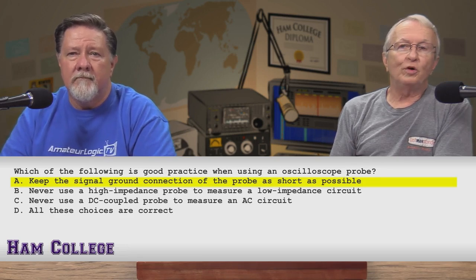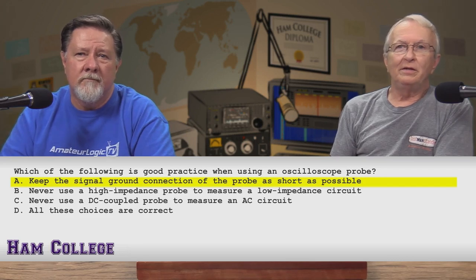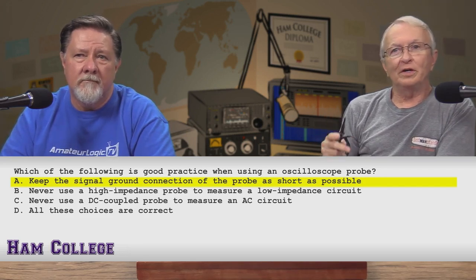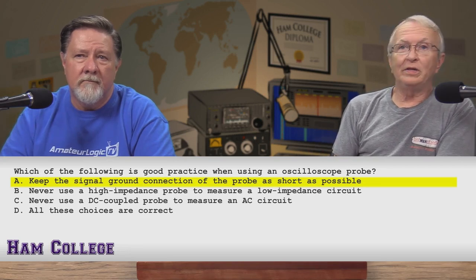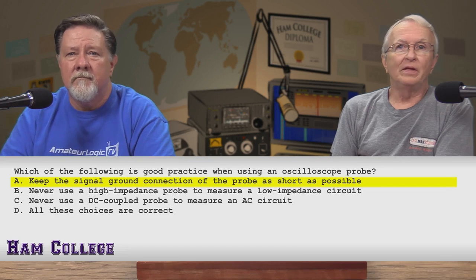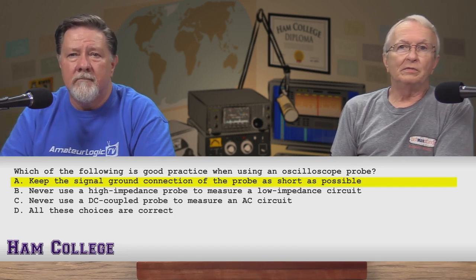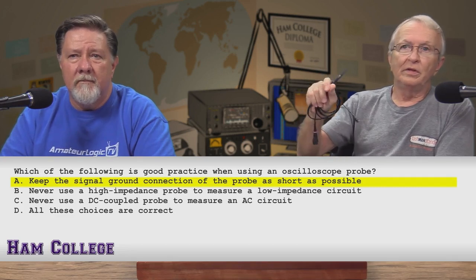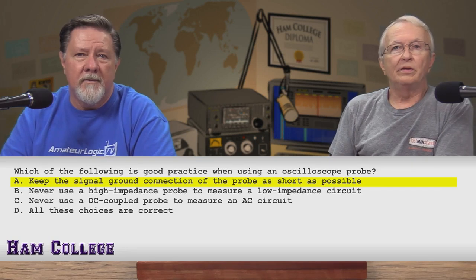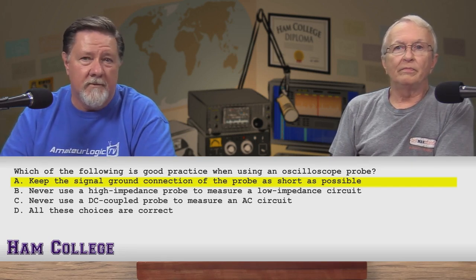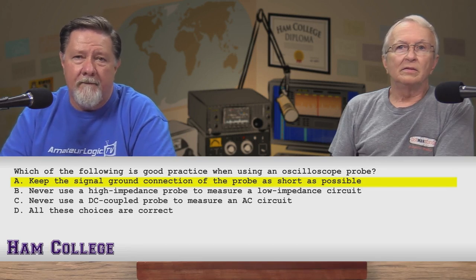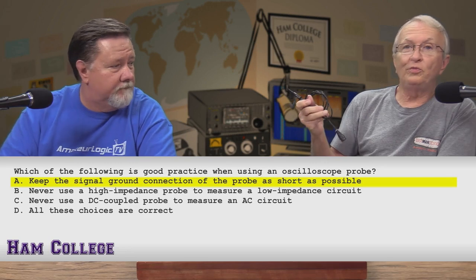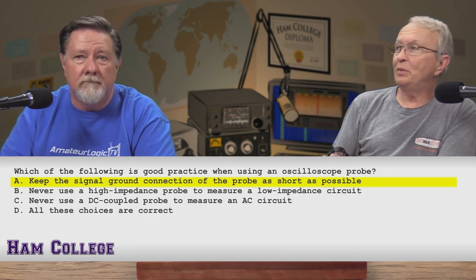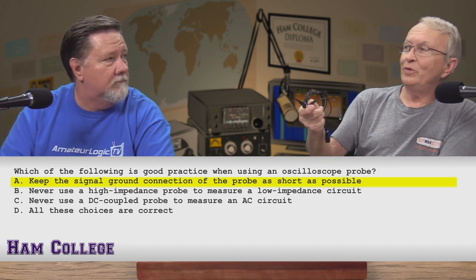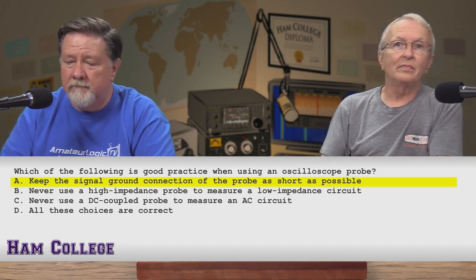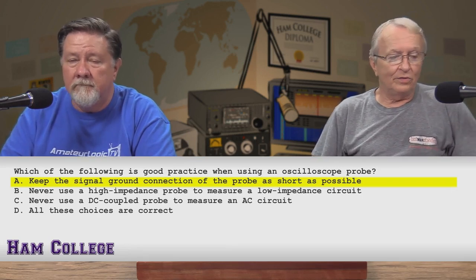Never use a DC coupled probe to measure an AC signal. No, you do that just about any time you turn your scope on, it comes on set for DC, and you switch it to AC if you want to. It doesn't hurt a thing if there's DC on there, as long as you adjust your voltage. But it's the same probe, right? Same probe, so that's why I didn't think that was it. All probes, scope probes that I know of, are DC coupled, because you can measure DC with them as well. So it can't be all of these choices either.